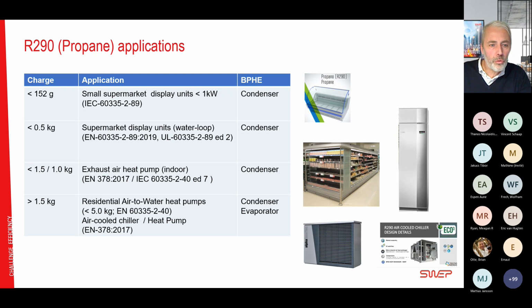And then lastly, for systems above 1.5 kilos, we see residential air-to-water heat pumps. Here we have one from Alpha-InnoTec, and it's typically a monoblock system where the full refrigerant circuit is placed outdoors. And it's governed by 60335-2-40, and you can have up to 5 kilos of refrigerant in that, or propane.